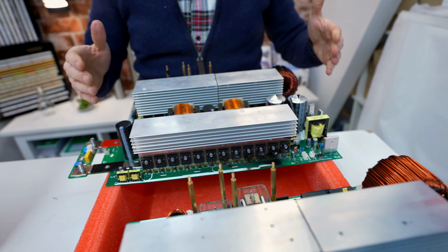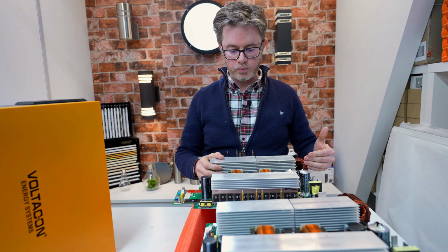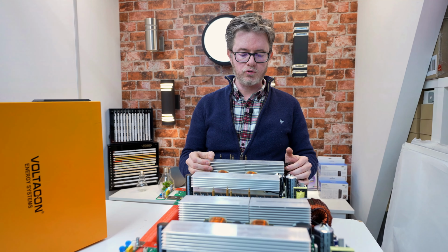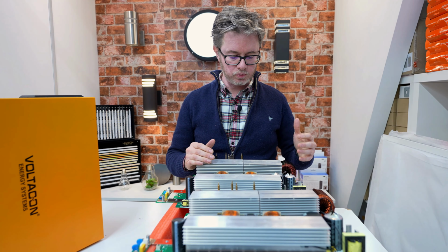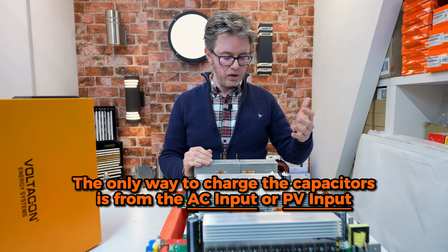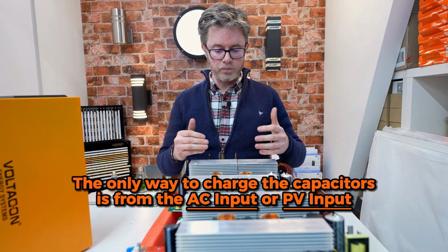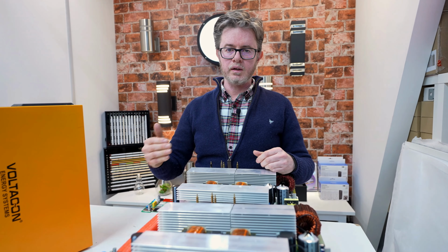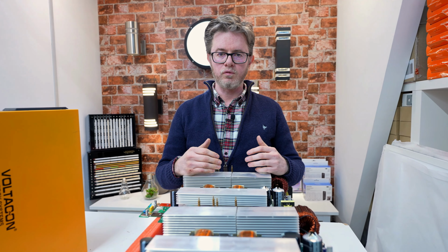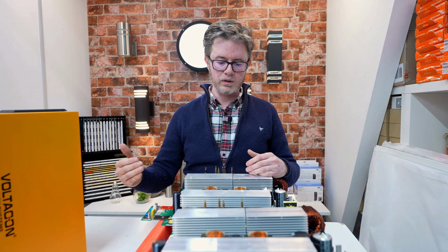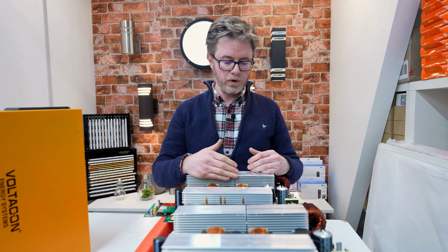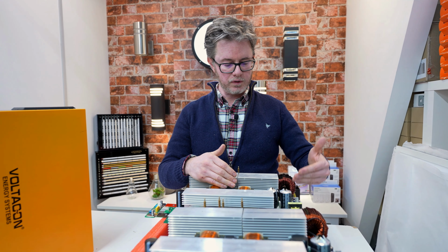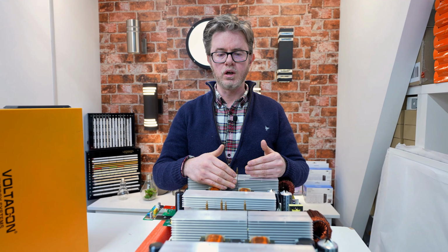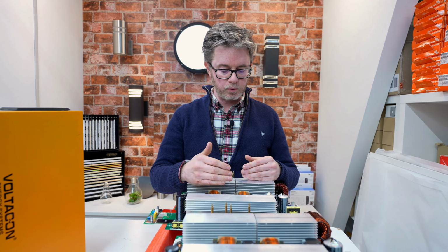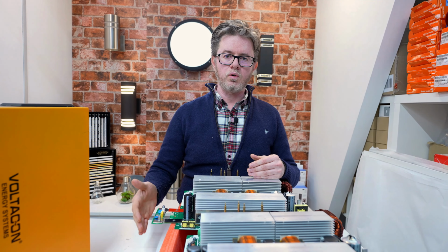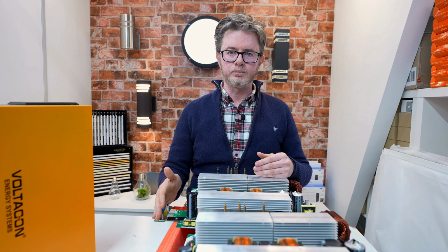So if you connect the AC input to the AC output, you don't have any control of this voltage anymore, because the only way to charge the capacitors is from the AC input or from the PV input. If you apply a random voltage on the AC output, you feed 230 volts without any control on the DC link, and this is going to overcharge the capacitors. The inverter is not supposed to protect itself if you apply the voltage wrongly.